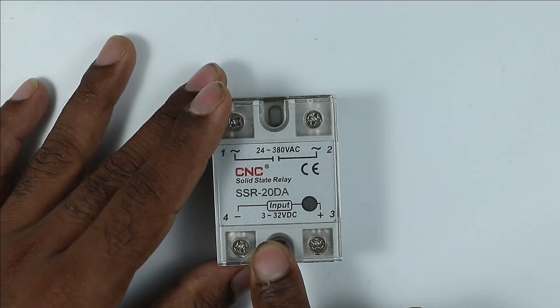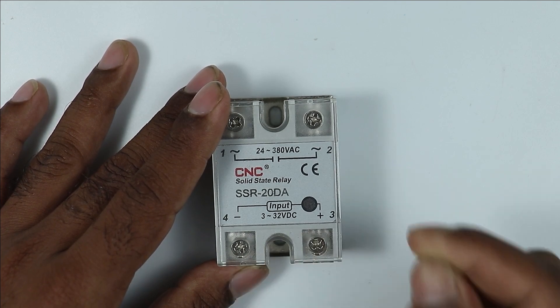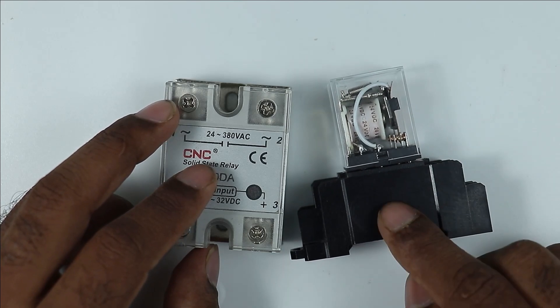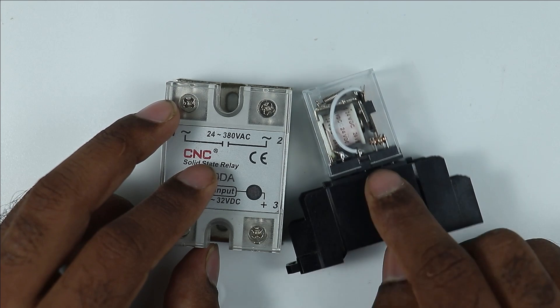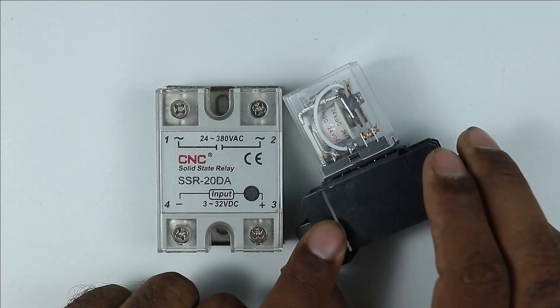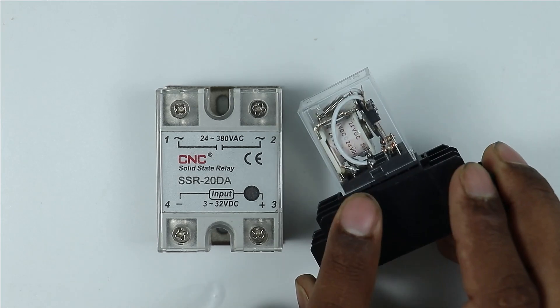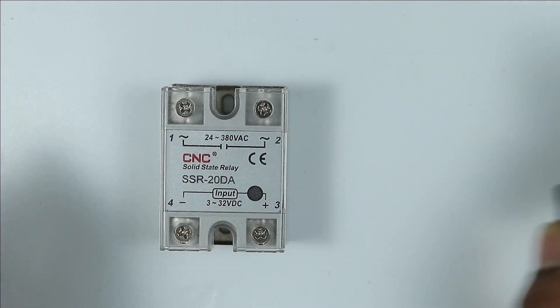When you are going to operate this relay, you have to provide 3V to 32V DC power supply. But for this normal type of relay, only the rated voltage needs to be provided — for example, this relay operates on 24V, so I have to provide exactly 24V DC. But this solid state relay can be operated on just 3V.